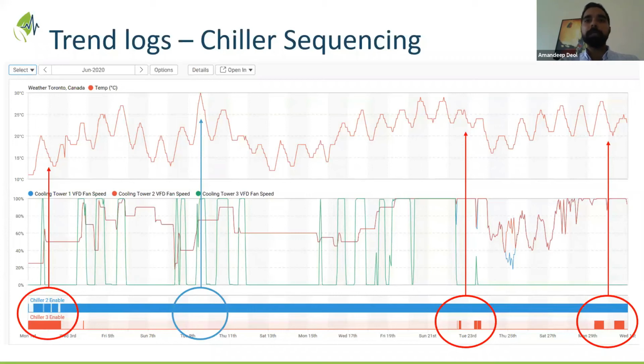So basically in this graph, you're seeing the weather temperature, and at the bottom graphs, you're seeing the chiller enable or disable point. So when you look at chiller 2 and 3, there are 2 chillers currently running. You look at the red circles, those are the times when both the chillers were running. And if you look at the third circle from the left, which is the red circle, at this point of time when the outside weather is around 22, 23 degrees C, you don't need the second chiller to come on.